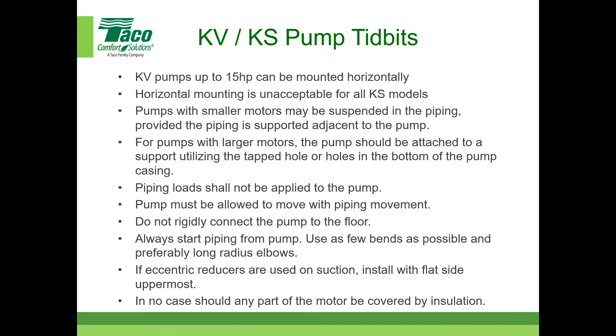I do want to mention this because, especially on chilled water applications, you see some insulation, and this is common. Don't insulate any part of the motor, right? You only insulate up to the top of the cover of the pump. Don't insulate any of the motor - that makes sense, and I think all of us can figure that out.